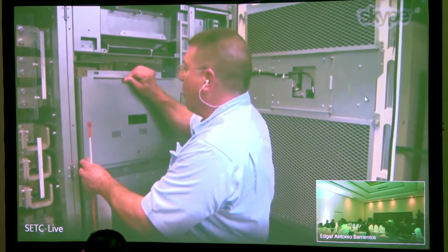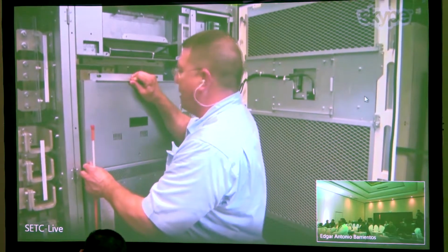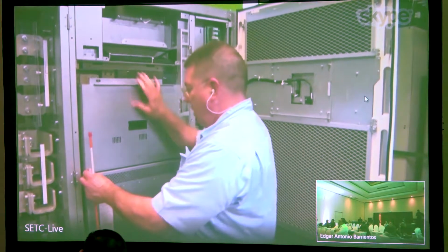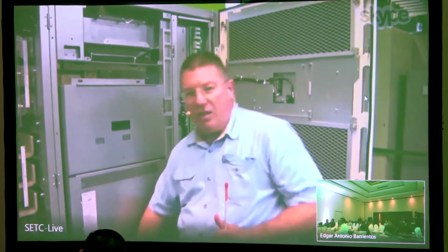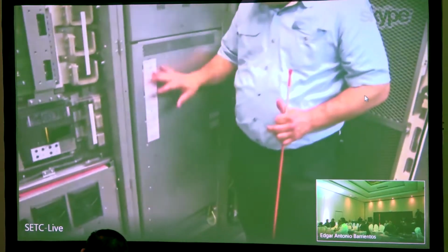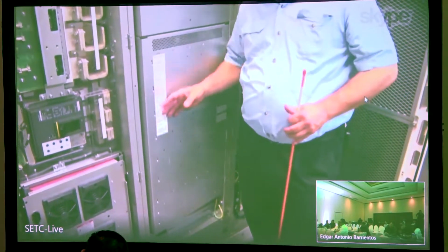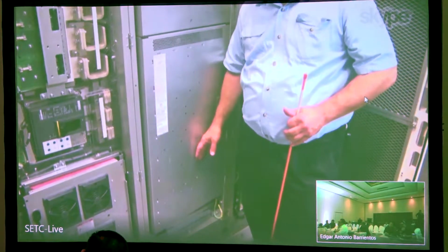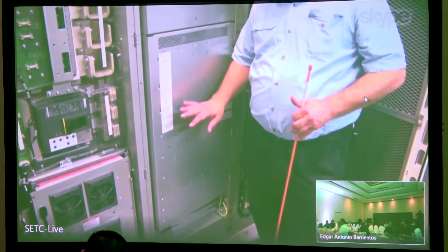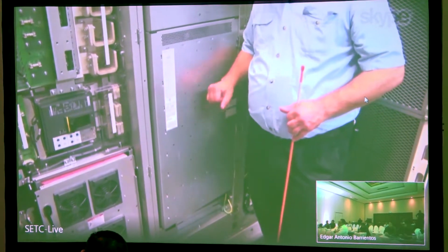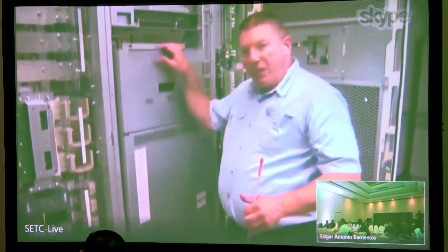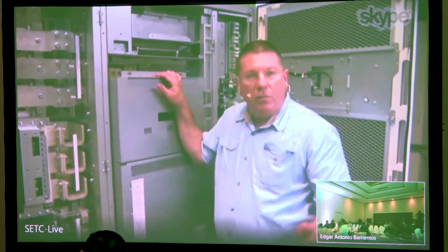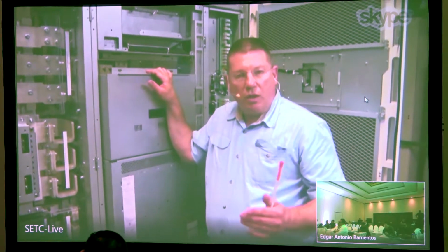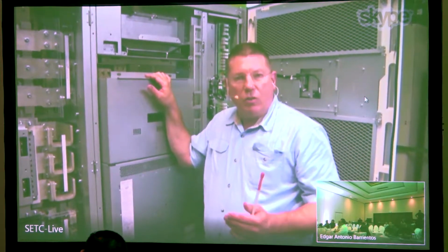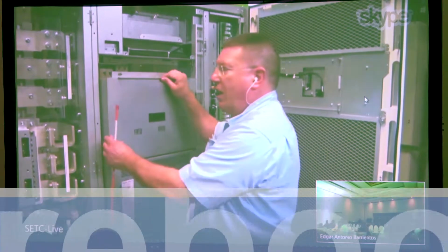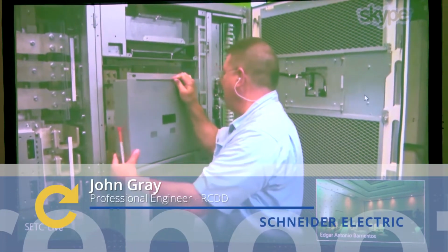Below this part of the cabinet, in the bottom part, is the main controller. This is where all of the distributed controls from the power cabinets, as well as the static bypass, get tied in with fiber optics. The fiber optics give us noise immunity, which is really an advantage in a UPS, so we don't have any interference with the control systems from EMF.